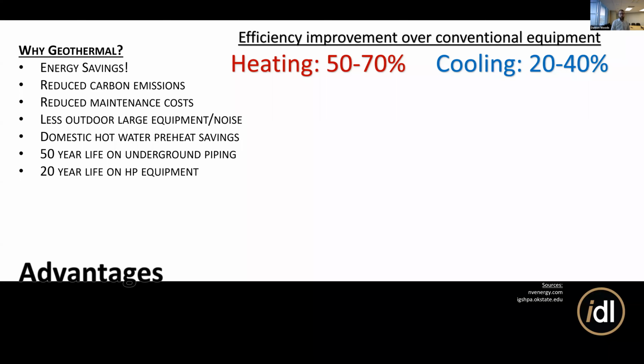It's going to switch into electric only mode. But even at, say, 30 degrees outside or 40 degrees, trying to pull heat from 40 degrees and force it up to, say, 80 degree supply temperature for the indoors, your efficiency is going to be quite low, versus trying to pull heat from the ground in a very conductive medium, water, at, say, 50 degrees or maybe even 60 degrees, and then ramp that up to an indoor air temperature of 80 to 85 degrees as your supply temperature. Much higher coefficients of performance for your equipment.